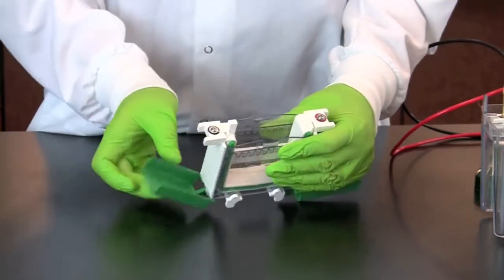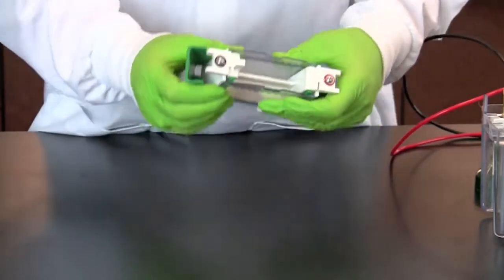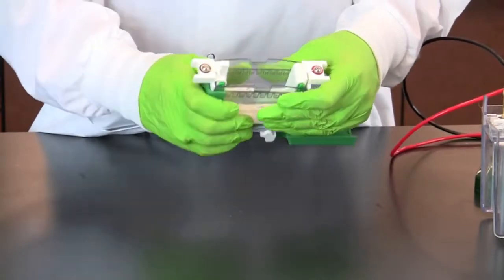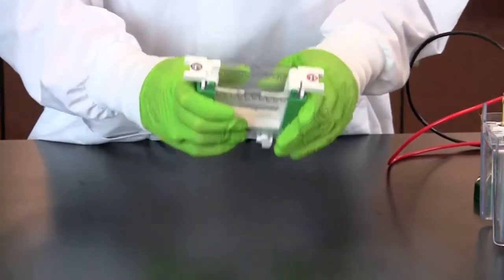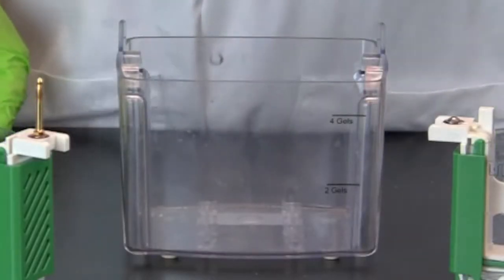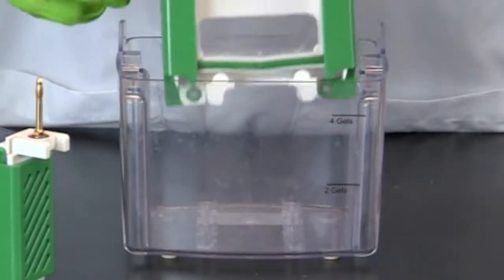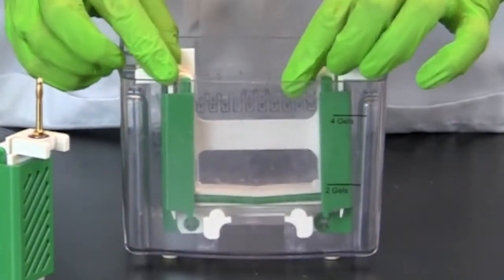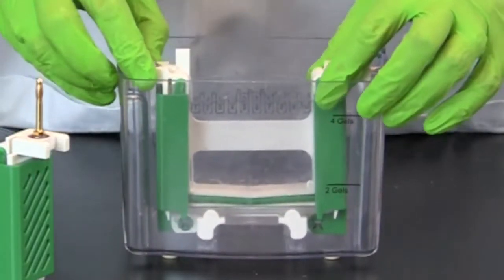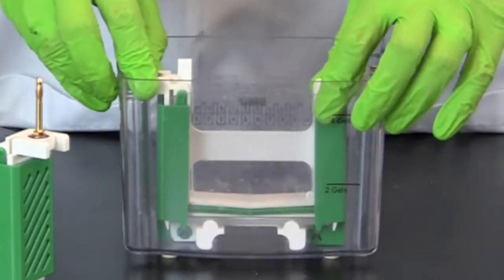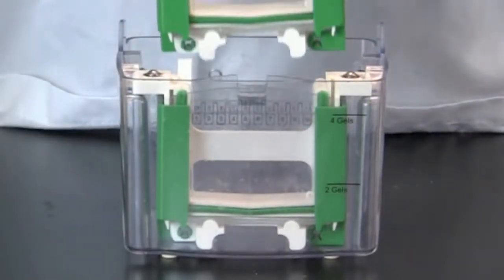Lock the green clamps over the gels. Lower the electrode assembly into the tank on the side of the tank with the plastic tabs. Make sure to match the red banana plug to the red oval on the tank. Lower the second assembly in the same manner.